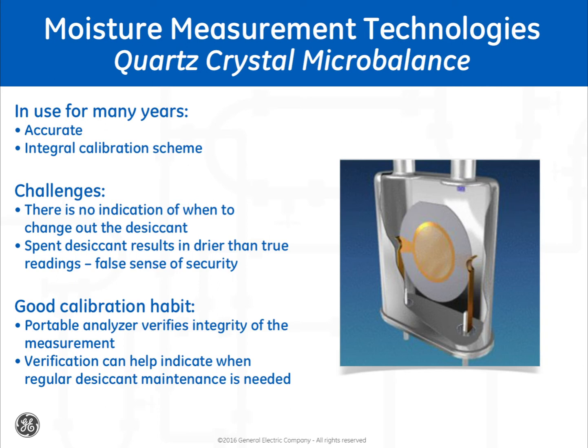A portable analyzer at the point of measurement can confirm that this analyzer is in calibration and properly responding to changes in moisture. If, for example, the reading from the portable is wetter than the dedicated analyzer after equilibrium is attained, this may be an indication that you need to replace the desiccant. These desiccant cartridges are a standard spare part. Since spent desiccant will result in drier than anticipated readings at the analyzer, a regular verification program will help identify a false sense of security.